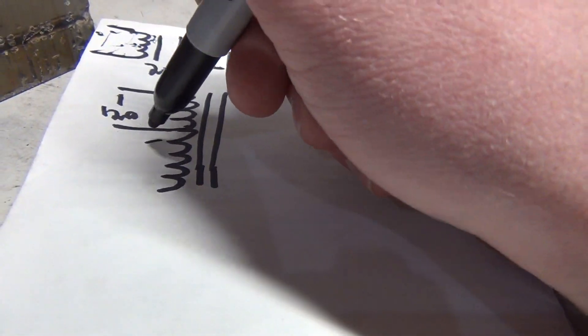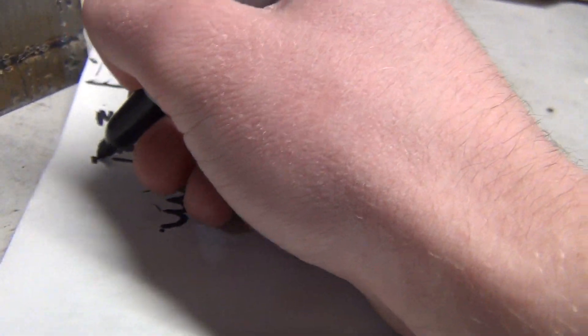So across here you got your 120 from here to here, but because it's all on the same core you get 120 here, and then say on this tap you get 140, 160, 180, 200, 240 right there. So you take your neutral here, there's your hot - neutral to hot is 120 - and then you take neutral and put it down to here and you get 240.